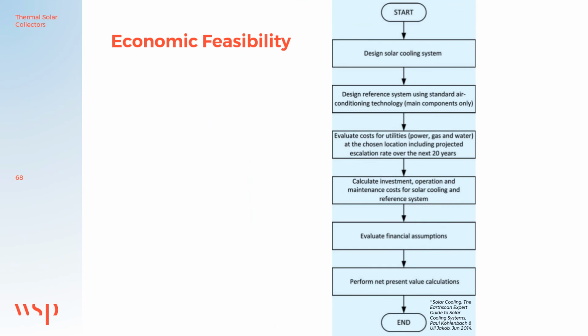Economic feasibility. This flowchart is one method to calculate the economic feasibility for a solar cooling system. This diagram shows the method and steps required to utilize the net present value method. Each individual step needs to be completed in the order shown. In most cases, we have to present the method to evaluate whether a solar cooling system has a lower or a higher lifetime cost than a standard conventional air conditioning system of a similar size. The technical design as well as the economic viability are interlocked with each other. Changing one will have an effect on the other. If this is the case, an iterative calculation process will have to be followed.